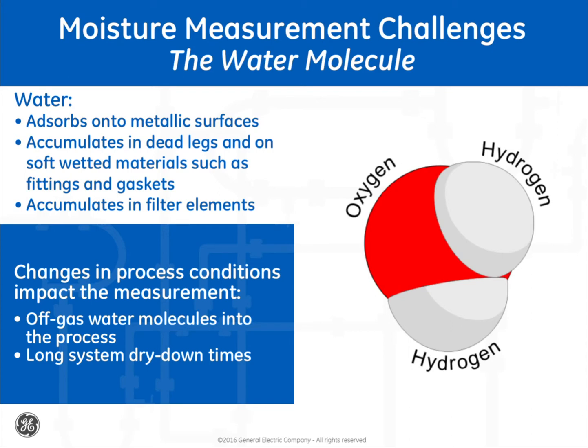The measurement of water vapor in gases and liquids offers challenges not typically found in the measurement of other process contaminants. Water molecules adsorb onto metallic surfaces and accumulate in dead legs, fittings, and gaskets, and in filter elements. Changes in process conditions, such as an increase in temperature, will lead to off-gassing of these water molecules into the process gas, or will impact the measurement at the sensor. This adsorption will lead to long system dry down times.